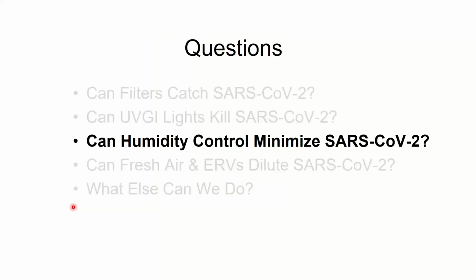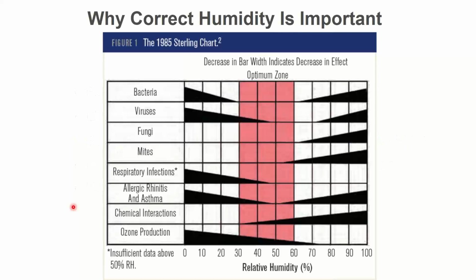So can UV lights kill COVID? Yes, they can, but not with the UV lights that you guys are using on HVAC systems. So kind of more of a no to that answer. Can humidity control help us minimize COVID? So you probably have seen this chart. It's been around forever. And by forever, I mean 1985. This is directly in the ASHRAE handbook. It's called the Sterling chart. I assume somewhere there's a footnote that says someone named Sterling made it, right?